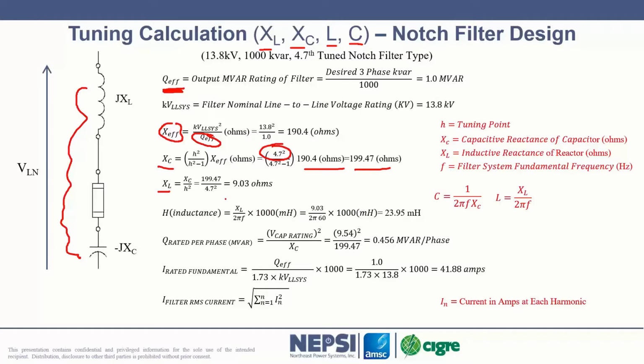So in this situation, you're coming up with those values. You come up with your value of X of C, which then allows you to calculate the rated kVAR of the capacitor. But again, now we need to pick, well, what voltage are we going to come up with? What capacitor voltage are we going to pick? Well, you have to calculate, well, what is the voltage here, right? We have harmonic current coming down. Harmonic current times this impedance creates voltage at each of the harmonic frequencies. Plus we have the 50 Hertz value of voltage at the fundamental. They must all be added together to come up with a peak voltage rating of the capacitor. And then from there, we can then come up with a capacitor kVAR rating based on a capacitor voltage rating. Fundamentally, that's what we're talking about doing. And we're going to talk about that in a moment.